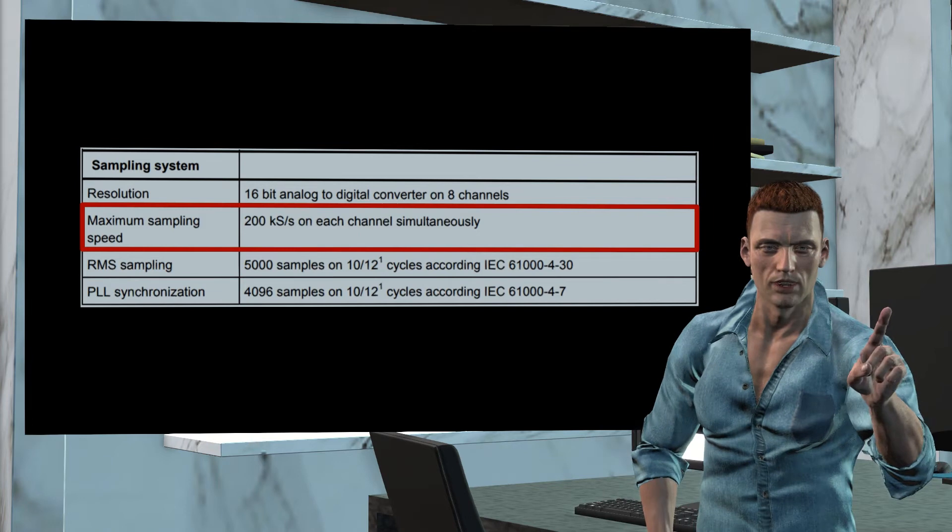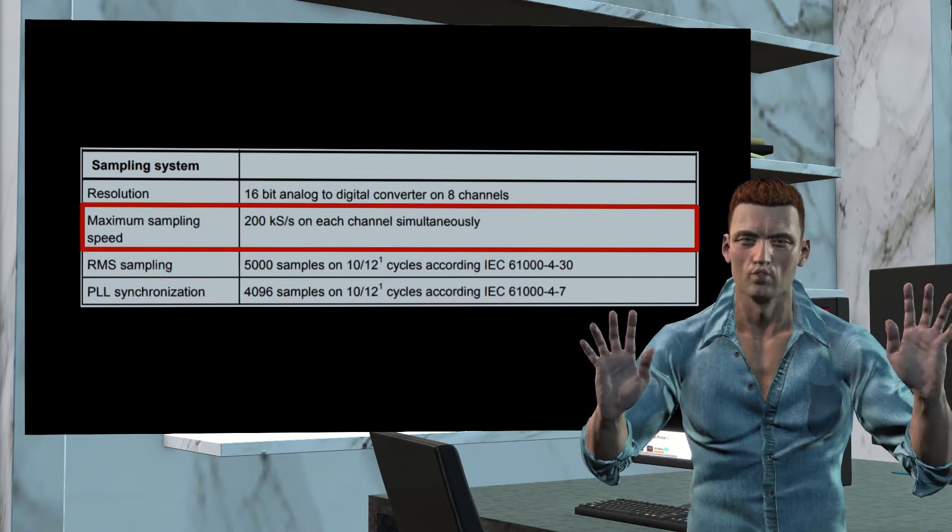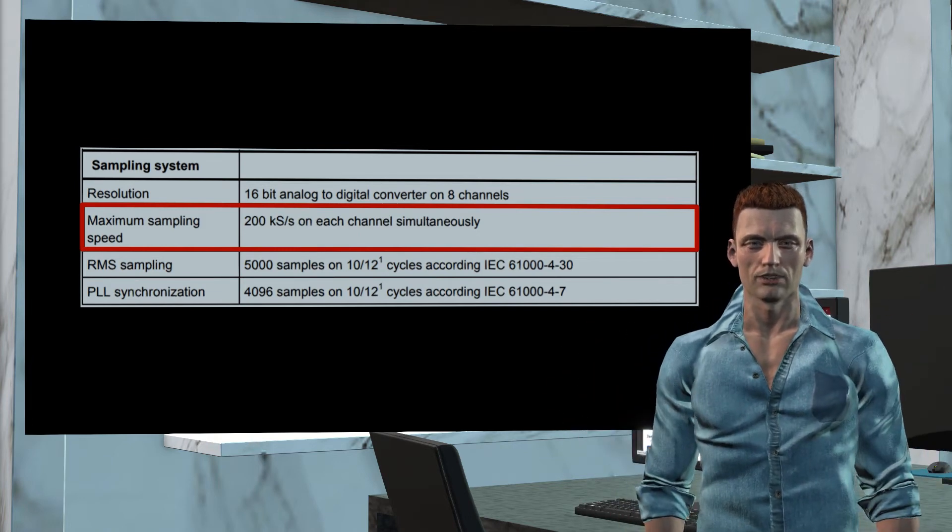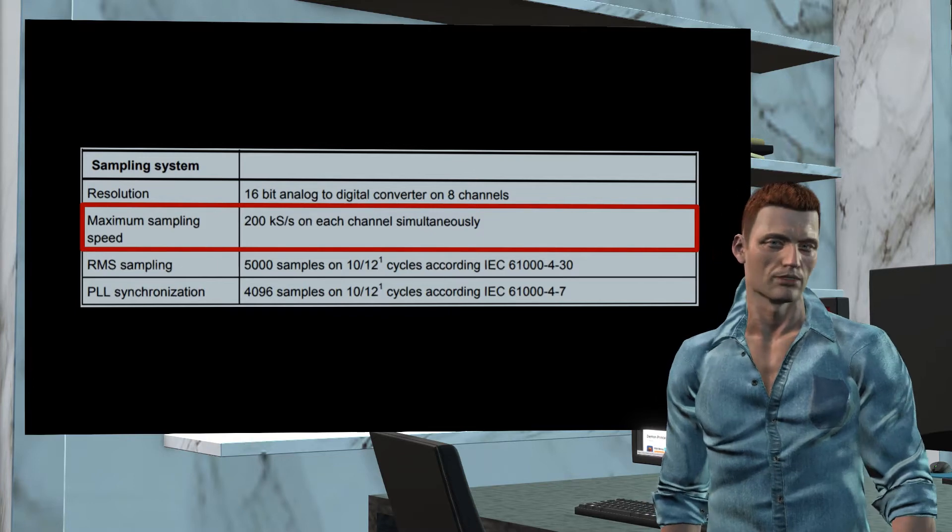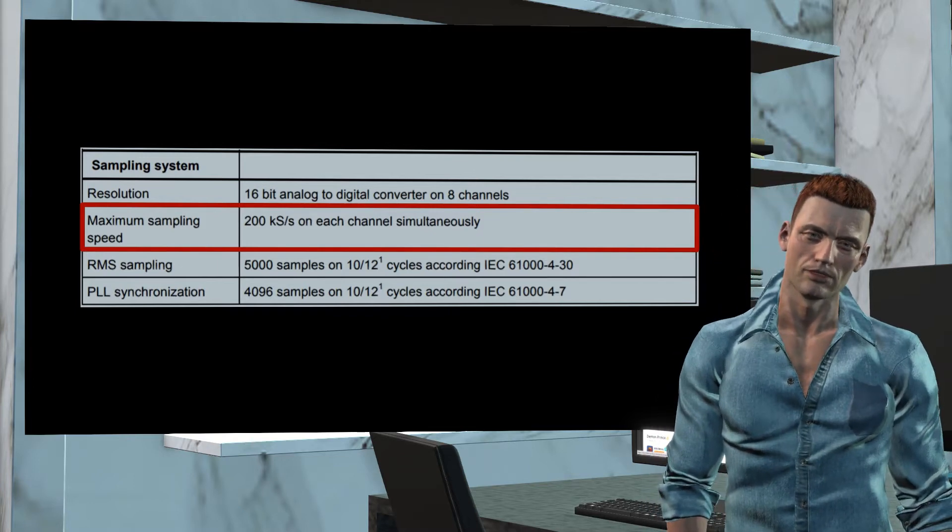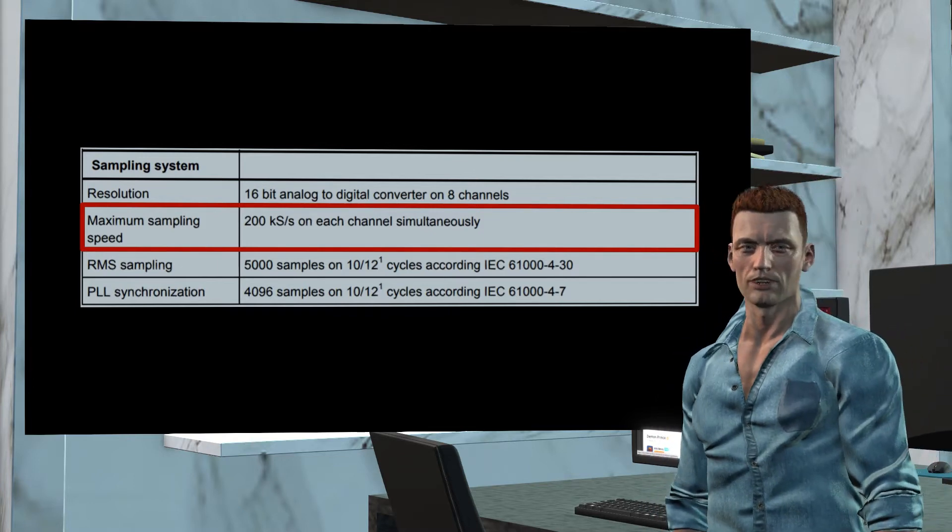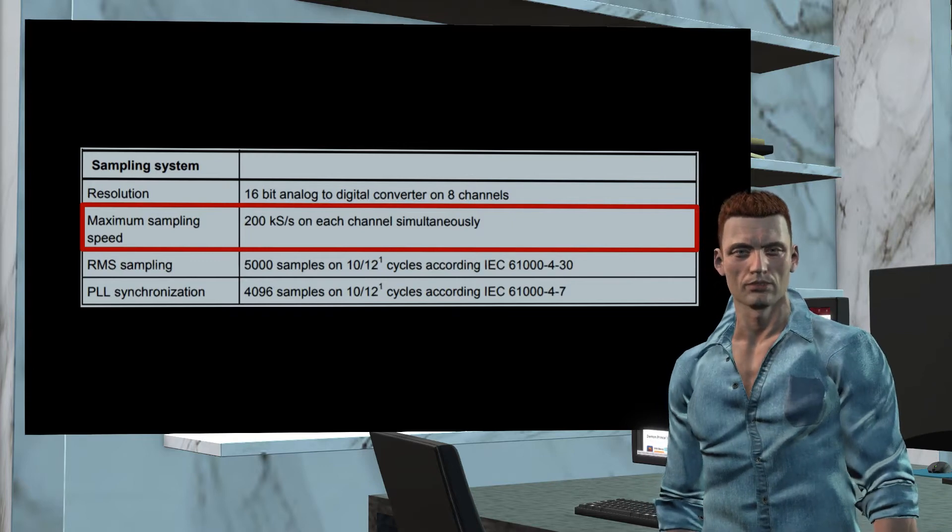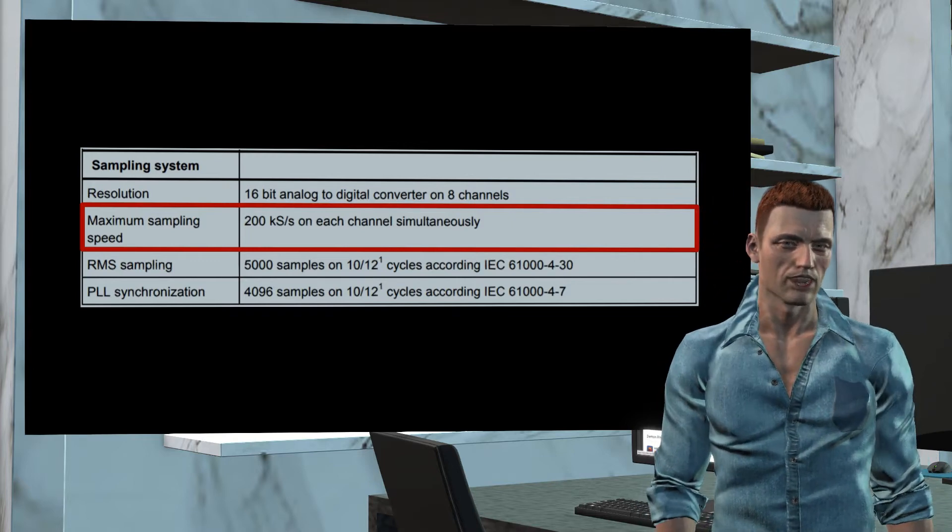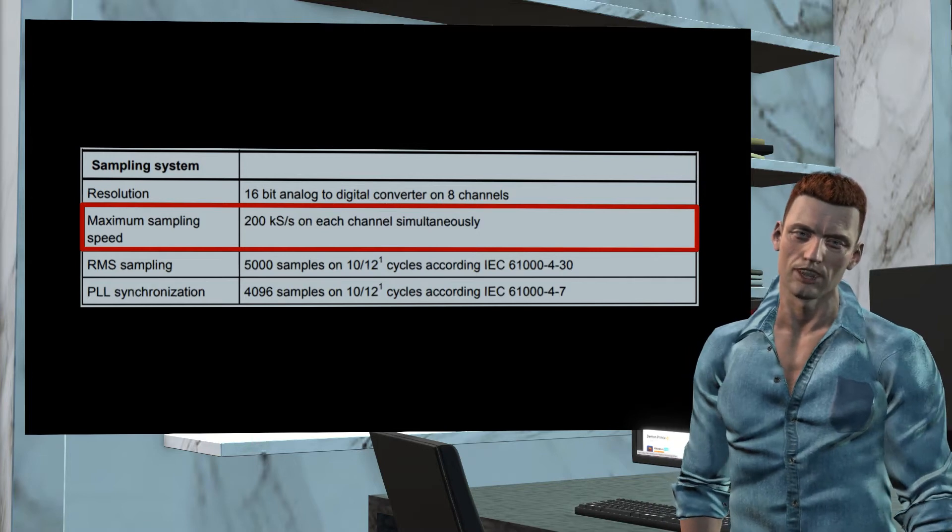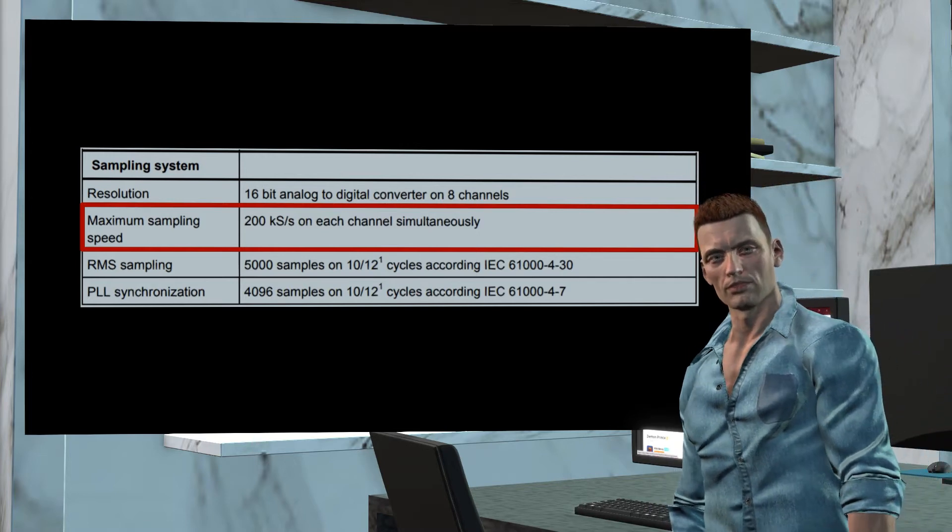For the recording of effective values or RMS we have that the equipment obtains 5,000 samples every 10 cycles at 50 Hz, that is, 5,000 samples every 200 ms, or what is the same, 25,000 samples per second, according to the IEC 61000-4-30 standard.